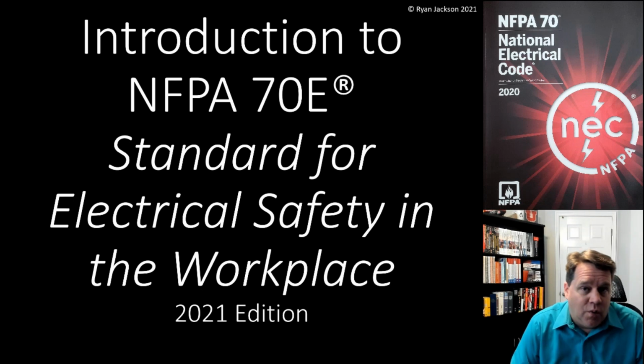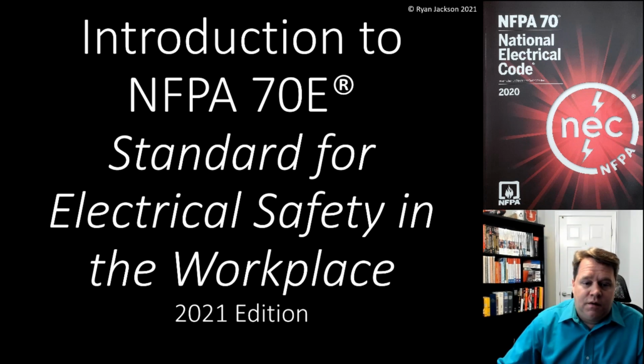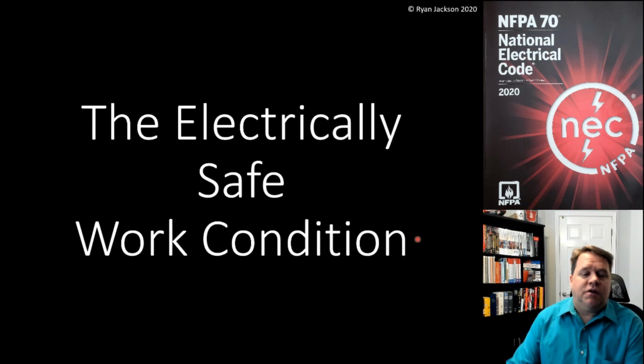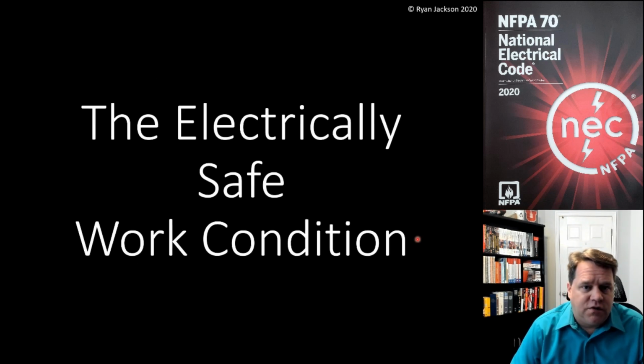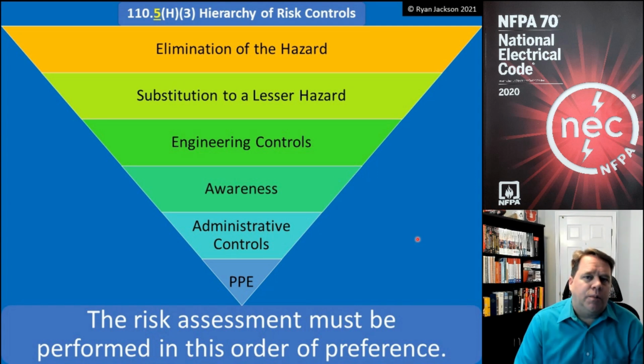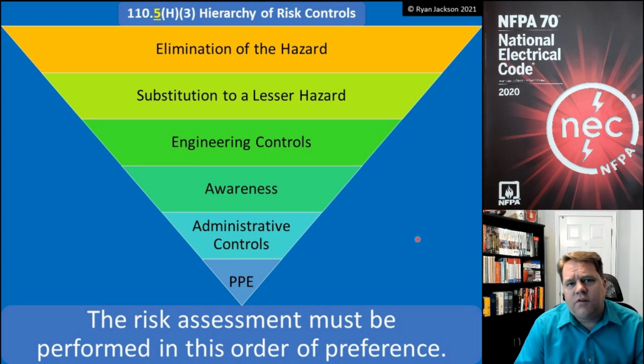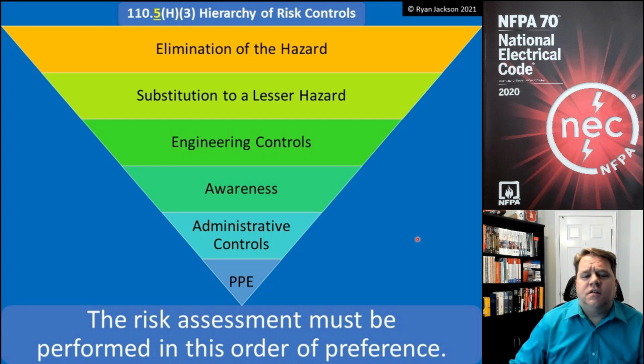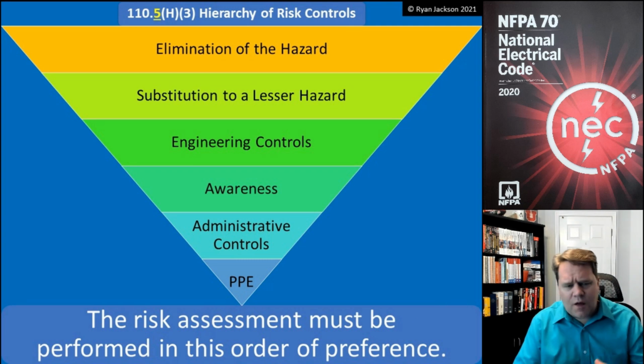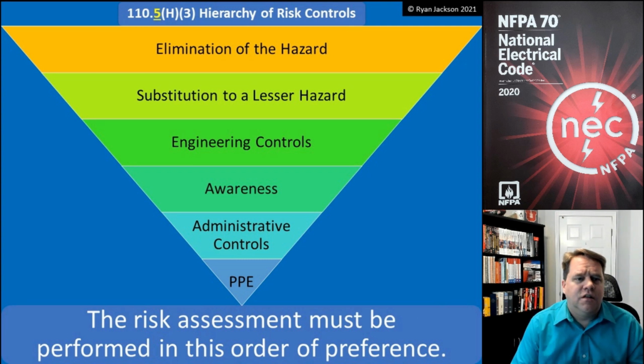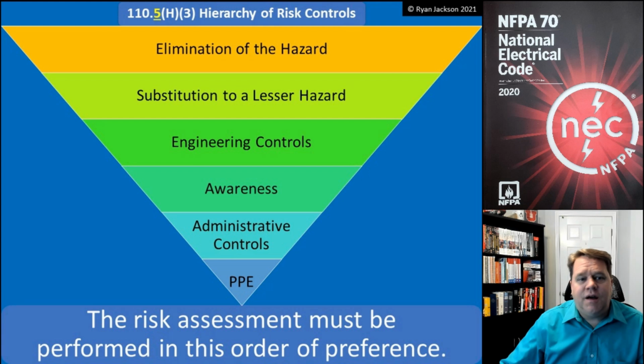This is based on the 2021 version of 70E. And again, we're going to be talking about an electrically safe work condition. So bouncing around through a couple of different sections here in the standard, I want to start very quickly with a concept in 110.5H3, which is the hierarchy of risk controls. It says that when we're doing a risk assessment, we have to perform it in this specific order. The first thing that we want to try to do whenever possible is to eliminate the hazard. And then you'll notice the last option is personal protective equipment.